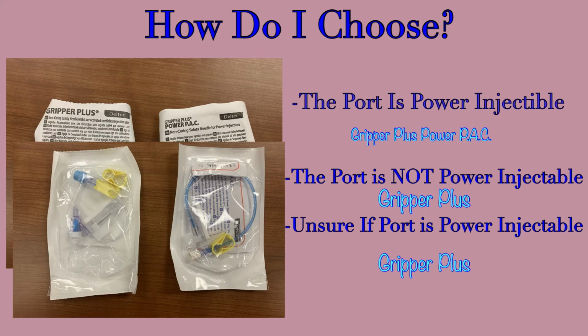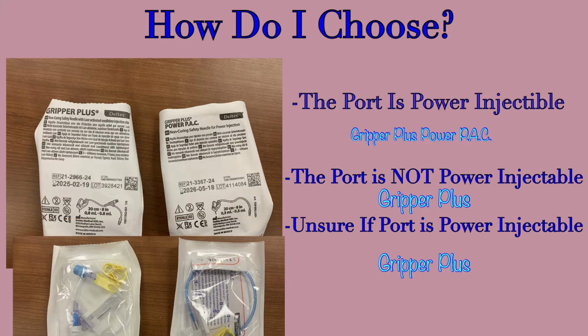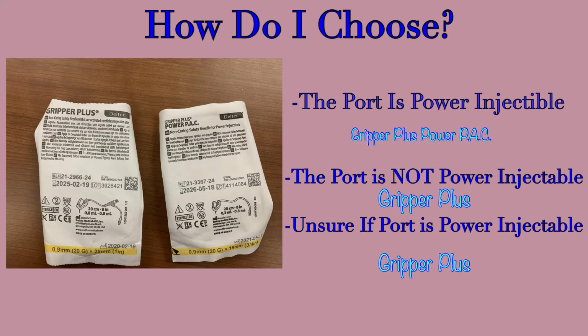The tubing attached to this needle is clear. It is not power injectable. To ensure that no one attempts to power flush a non-power injectable device, we will always default to the clear tubed Gripper Plus if we have not verified definitively that the port is indeed power injectable.